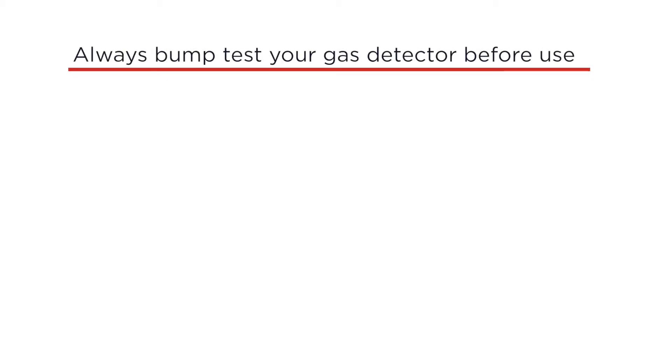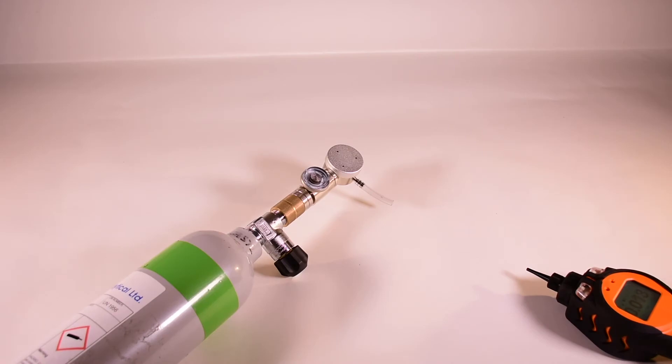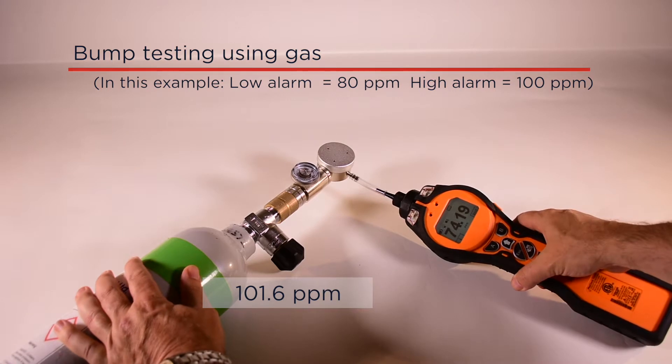Ion Science recommends bump testing before every use. Bump testing ensures the instrument is detecting gas accurately and that audible and visual alarms are working correctly. The best way to bump test is to offer your Tiger a known quantity of gas. Ion Science recommends using 100 ppm isobutylene. Connect your Tiger to the calibration gas — it should measure correctly, and an audio-visual alarm should trigger when the reading exceeds the alarm levels.